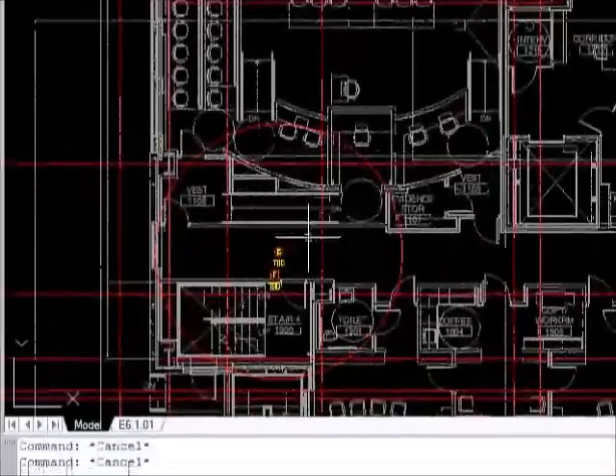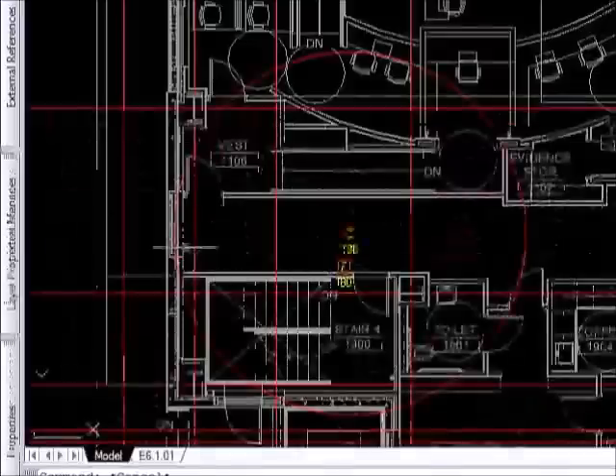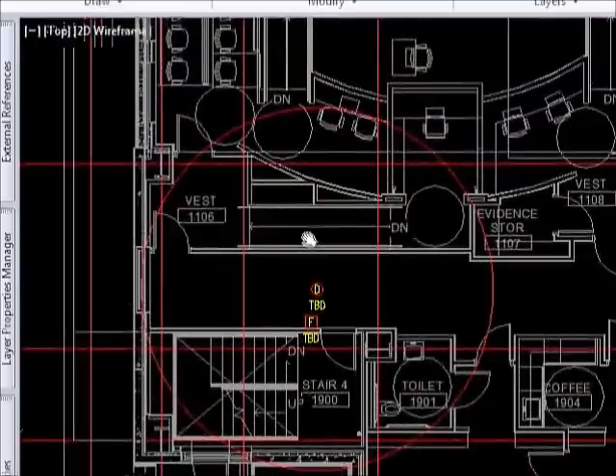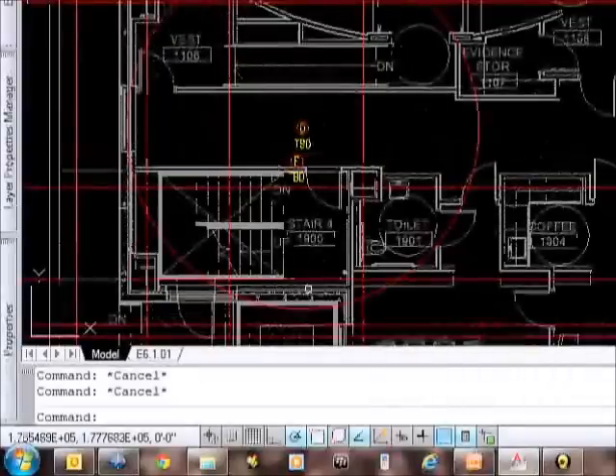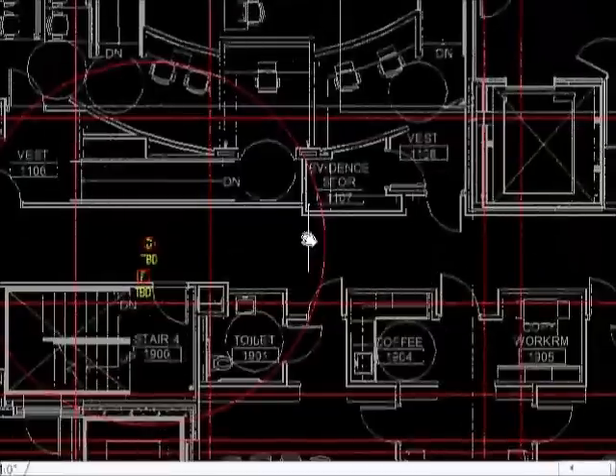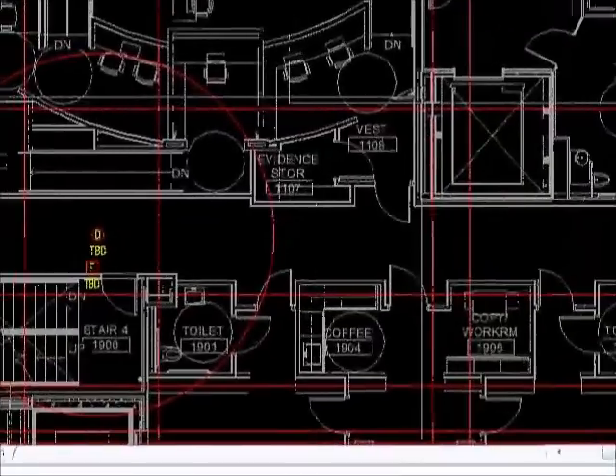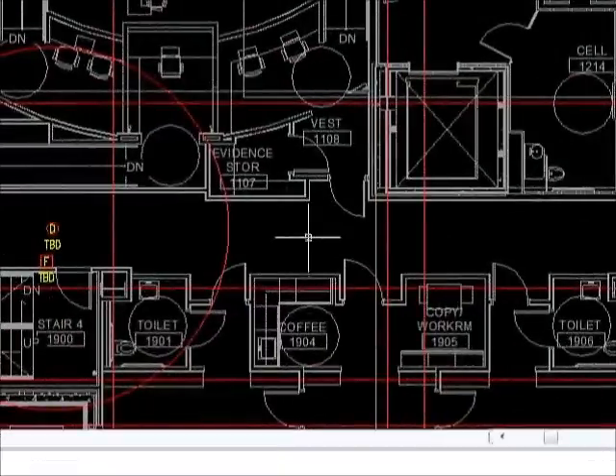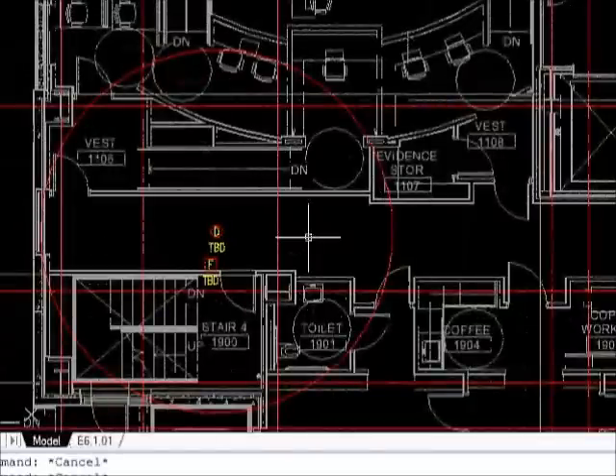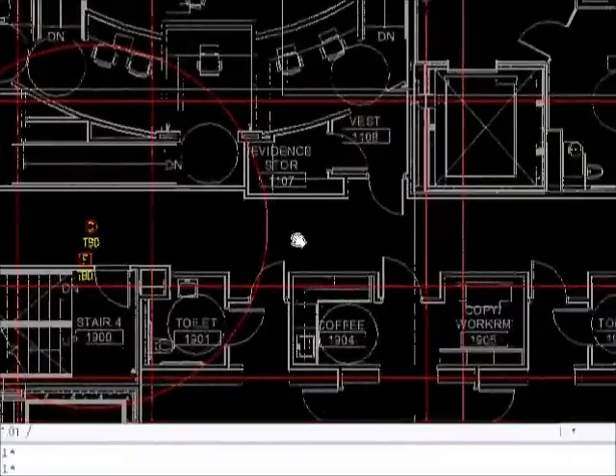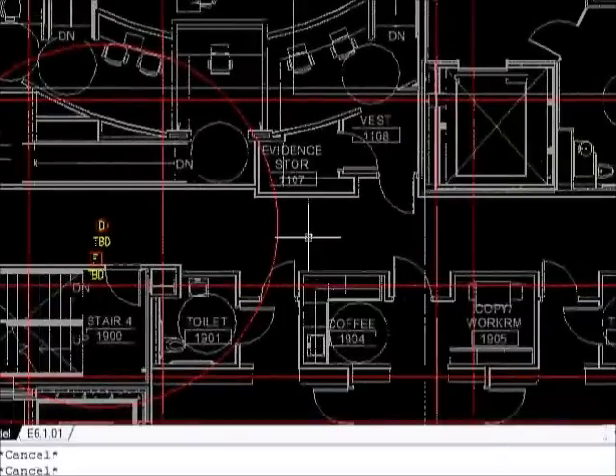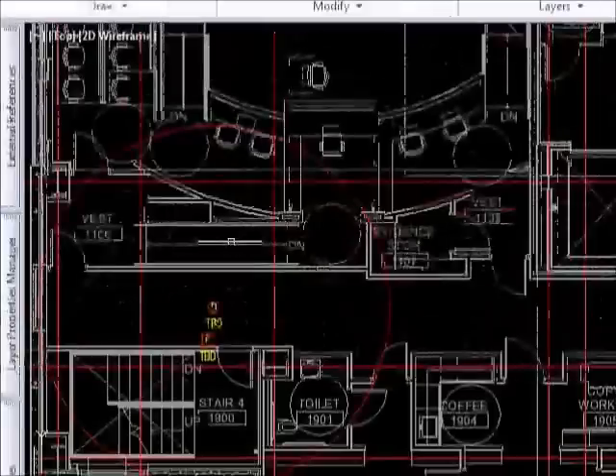Generally the smoke detectors are showing us a 30 foot diameter circle, so 15 foot radius around the device, which allow us to do quick placement. Again, you have to be aware of your ceiling conditions and so forth for special applications, but in general this will allow you to do quick placement on a smooth ceiling.